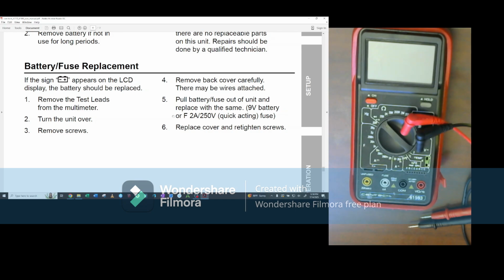Right here on step 5, this is where that mistake is. It says it has a 9-volt battery or a fuse, that's what the F stands for, a 2 amp, 250 volt quick-acting fuse. This should be a 0.2 amp, 250 volt. So in this part of the manual, this is incorrect, because everywhere else it's stamped with 200 milliamps, which is 0.2 amps. Just be aware that's a mistake.